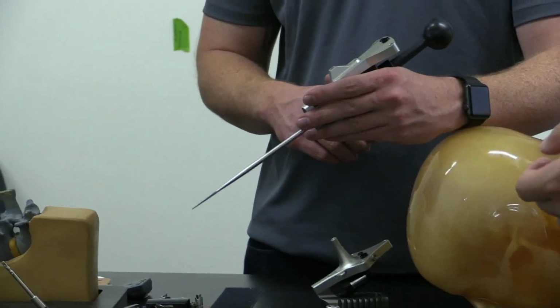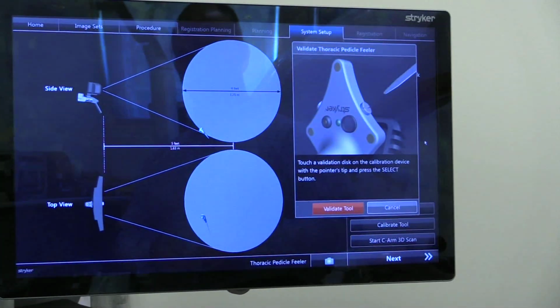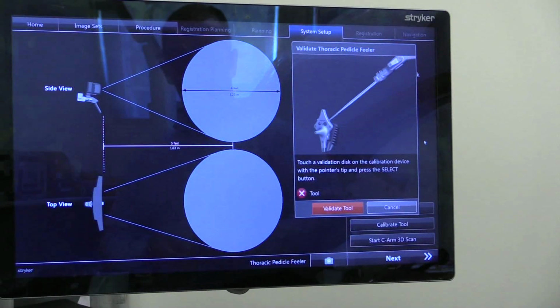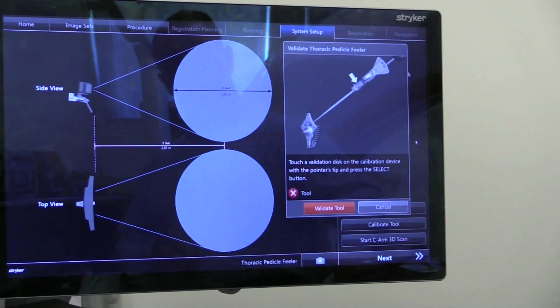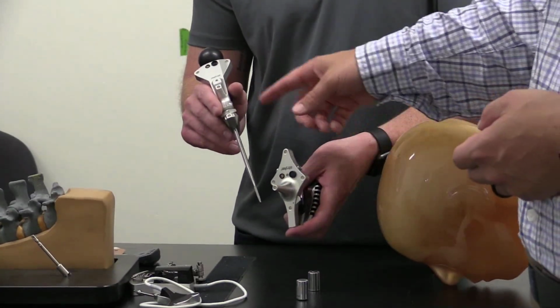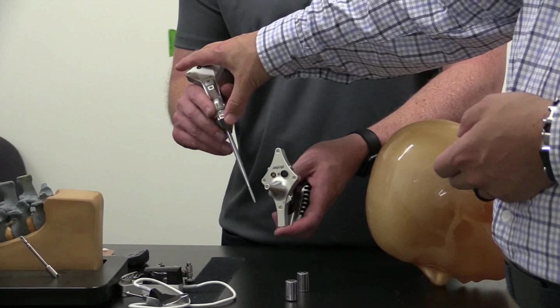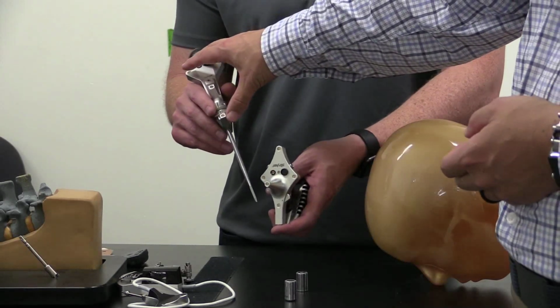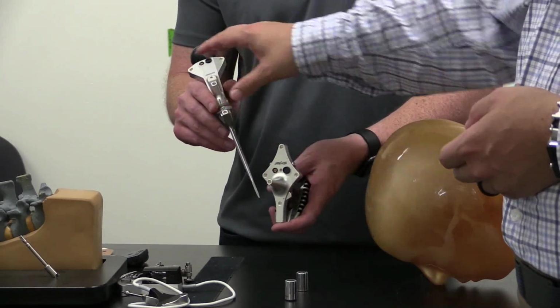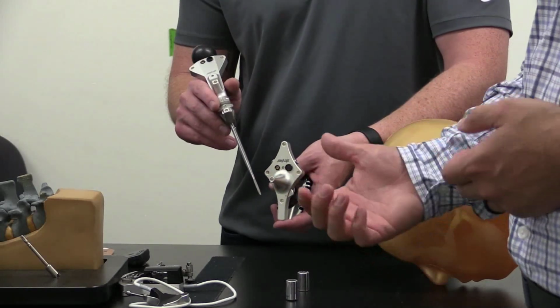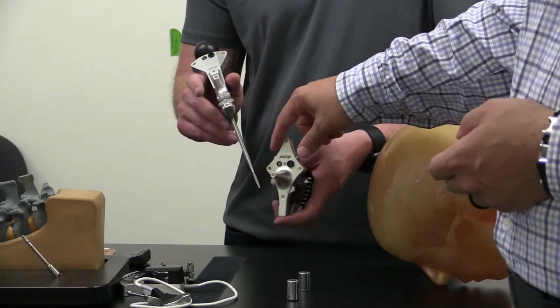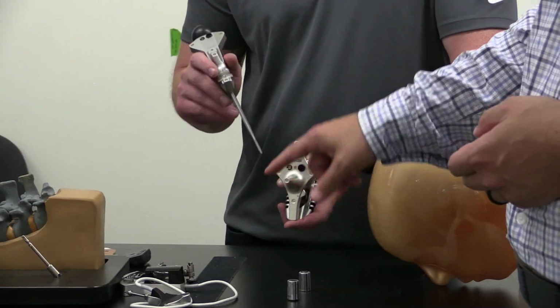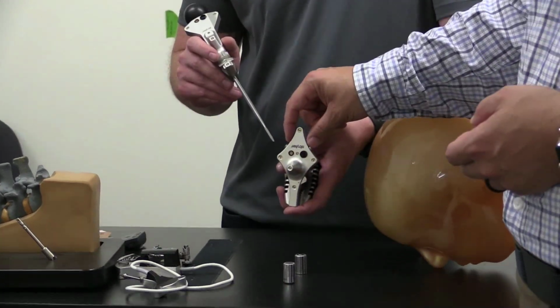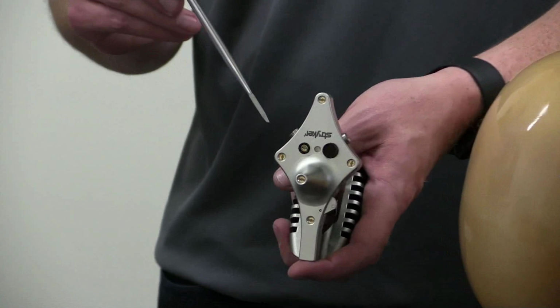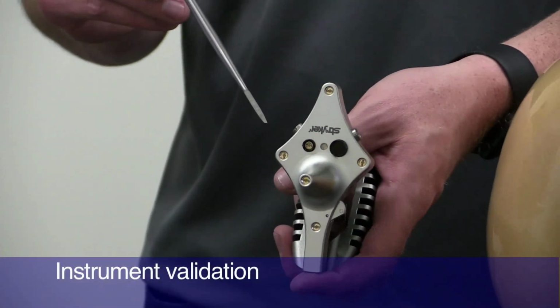It will come on. The screen will then give you the instructions to touch off on the validation disc. There are 2 validation discs, one on either side of the calibration device. All of the calibration is stored inside the computer for this thoracic pointer, so it knows exactly where the tip is in its X, Y, and Z coordinates. So this is going to validate. If you bring the tip within 22 millimeters of either validation disc, the system automatically knows that it's trying to achieve validation.